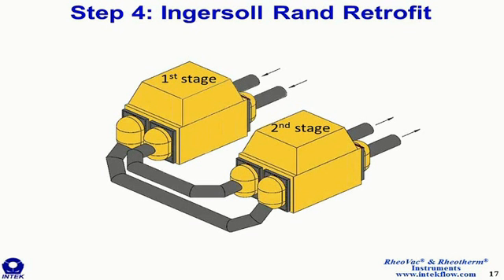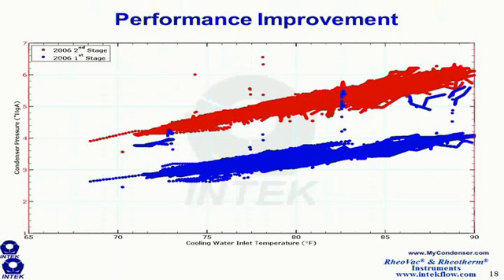And so I want to show some data from this condenser retrofit. The retrofit occurred in 2010. I'm going to show you data dating all the way back to 2006. So again, this is a similar plot to the one I showed you before, but with much more data. There's condenser pressure over on the y-axis, cooling water temperature on the x-axis. The red data is an entire year of data filtered for full load for the second stage condenser shell. The blue data is all of the data for the entire year of 2006 for the first stage condenser shell.